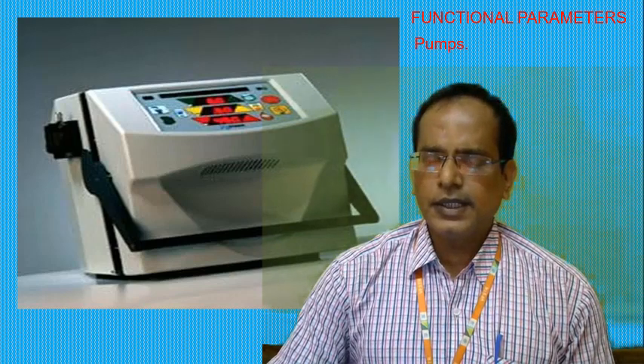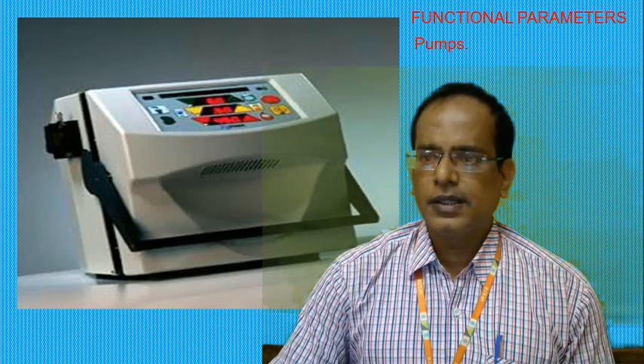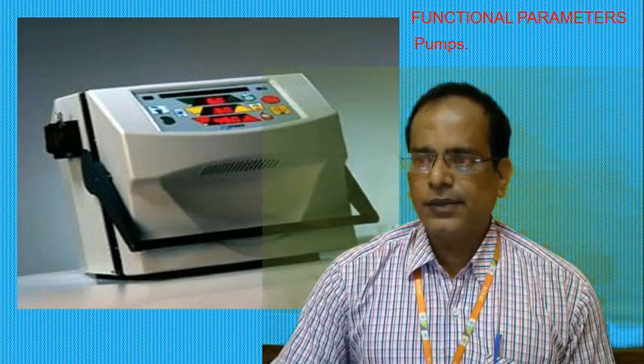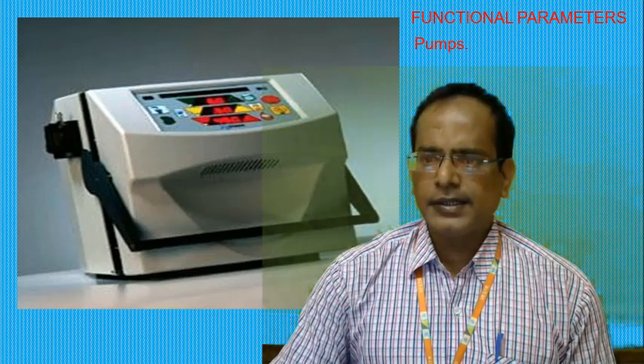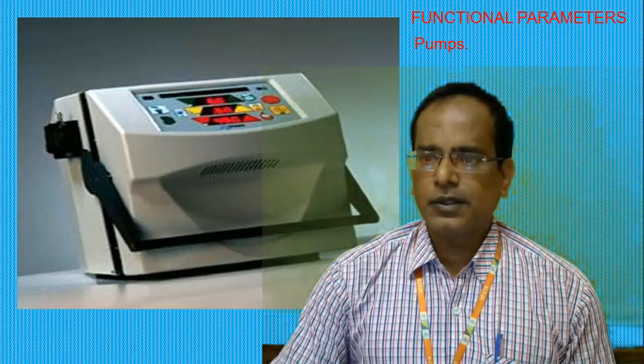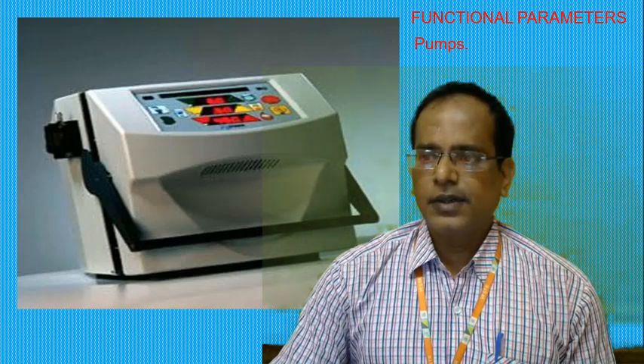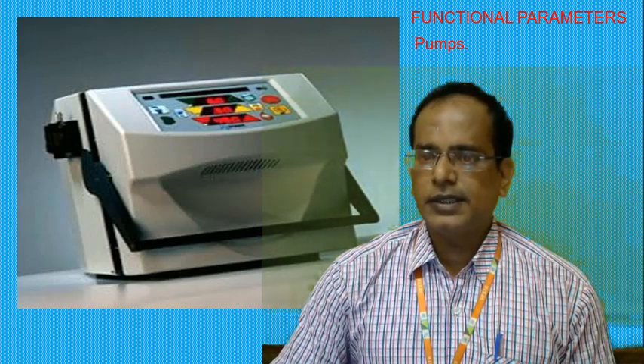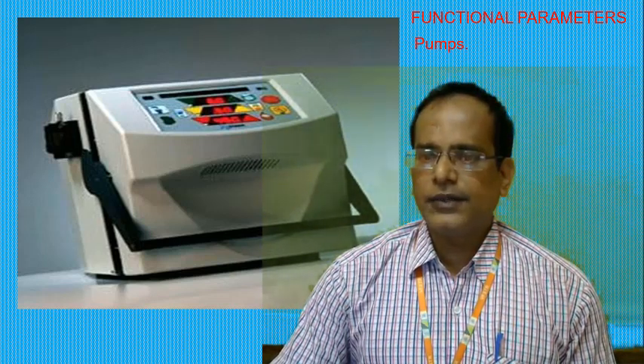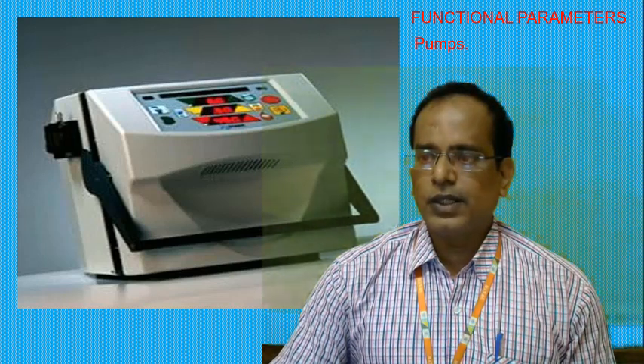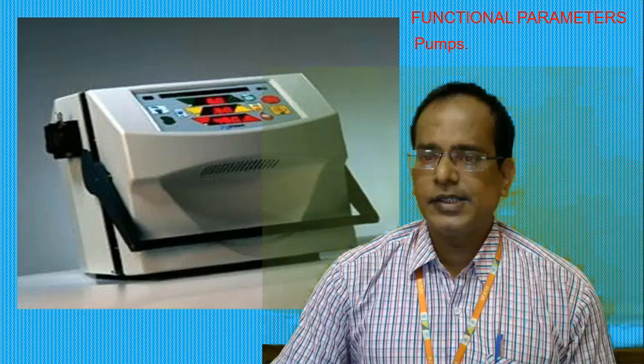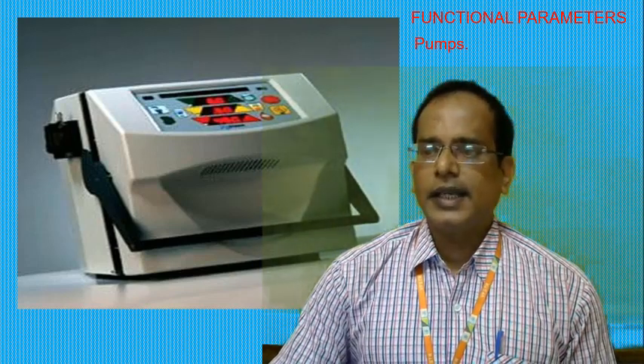The first functional parameter is pumps. Peristaltic pumps are commonly used for driving the various high-volume fluids in the machine — blood, dialysate water, and saline. This type of pump is convenient because it does not touch the fluid directly; instead, a section of flexible tubing runs through the pump mechanism where it is compressed by a roller to push the fluid forward.